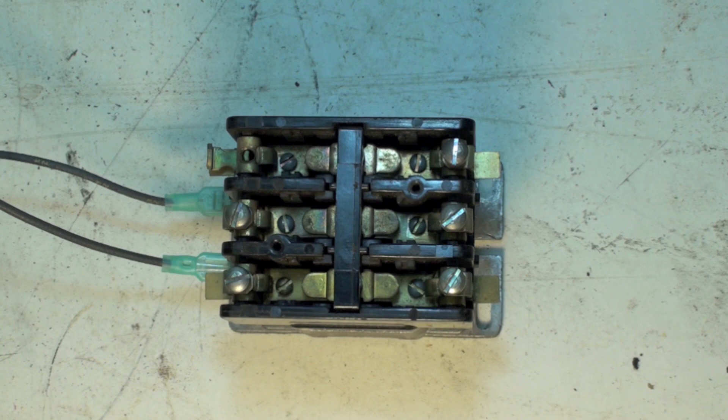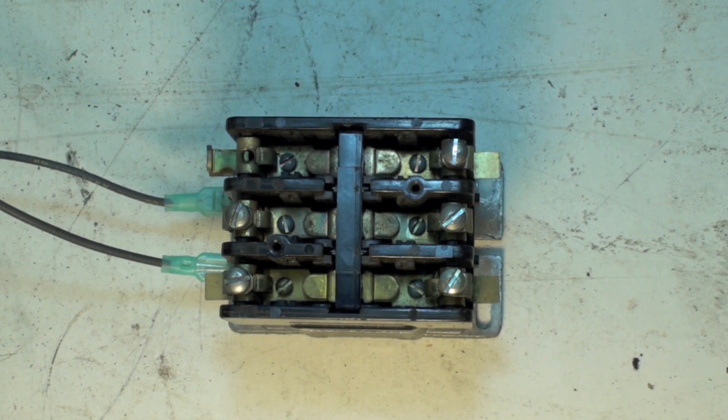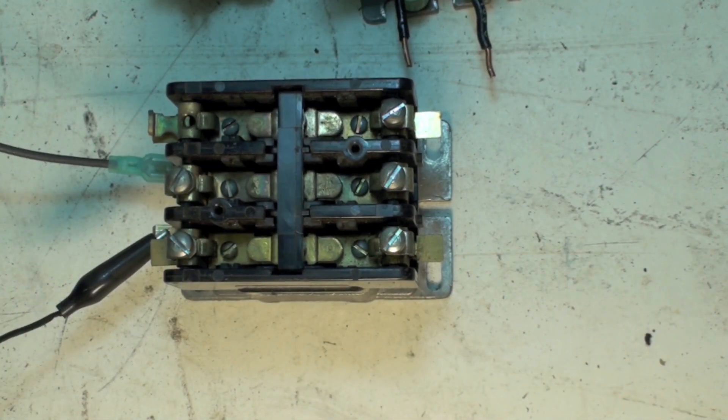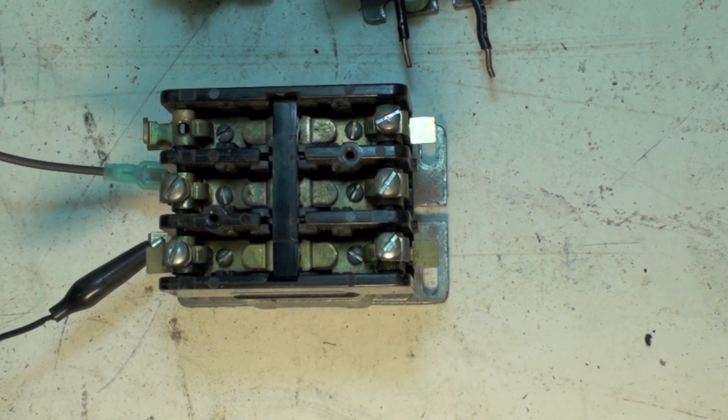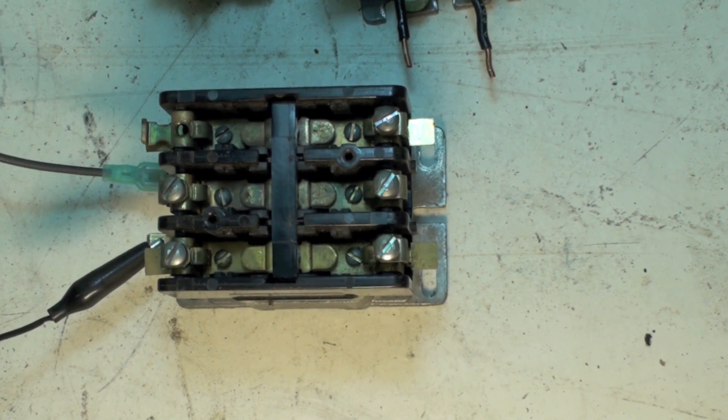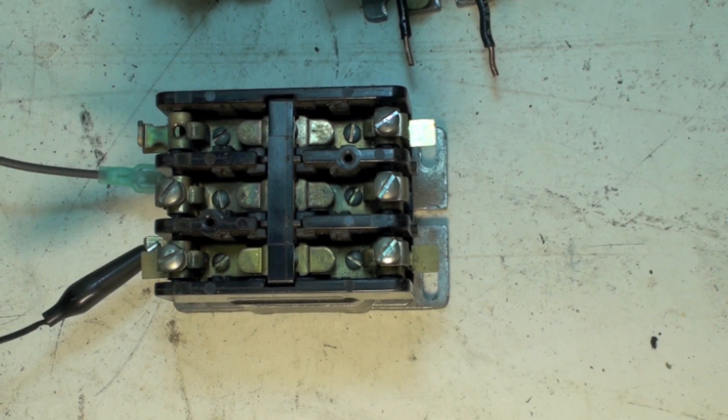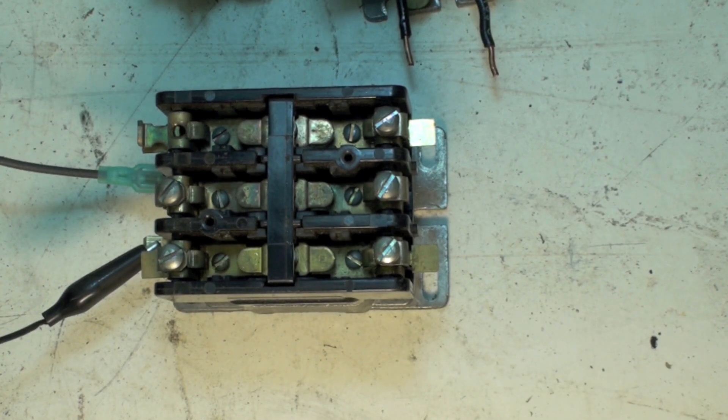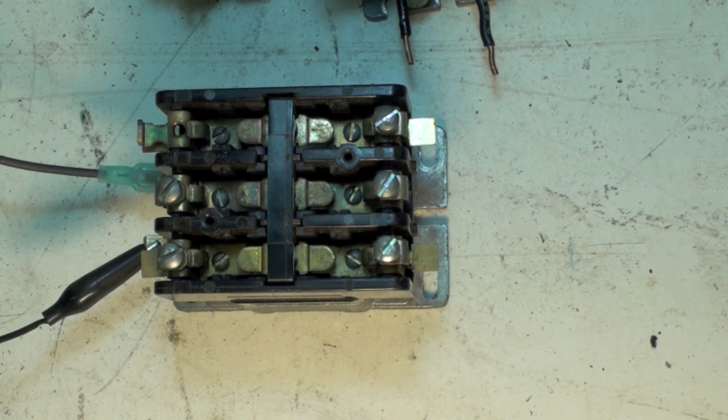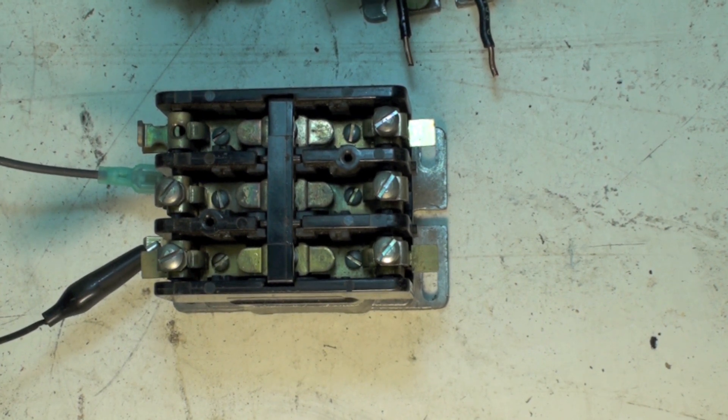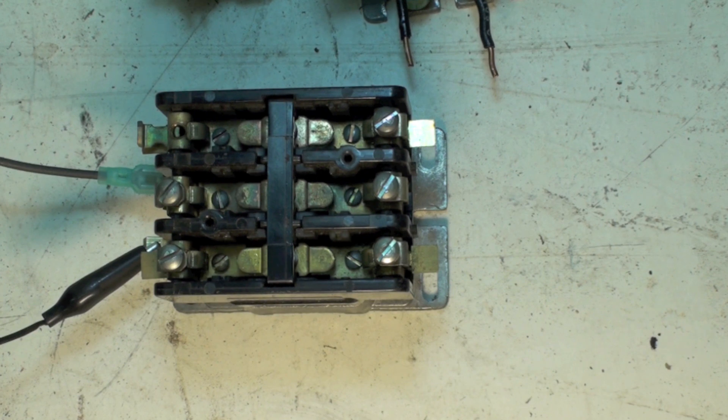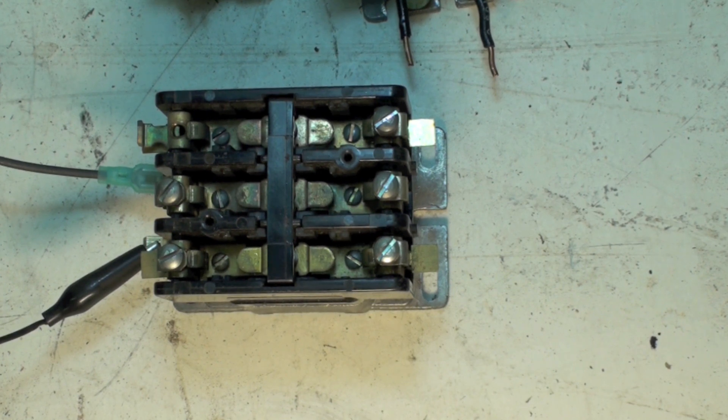There is no real hesitation on it. That's how they should always work. Okay, there I've just been able to kind of imitate a chattering contactor. I don't have one that does chatter, but it does kind of go like that. By the time you get to it, the contactor's probably pretty much toast.